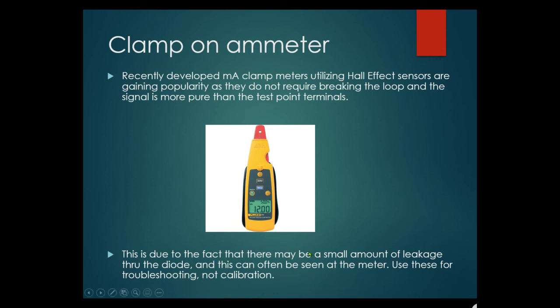There may be small amounts of leakage through the diode, which can sometimes be seen on the meter. Use these clamp meters for troubleshooting, not calibration. They're actually more accurate than test point measurements for current, but you still cannot calibrate from there.